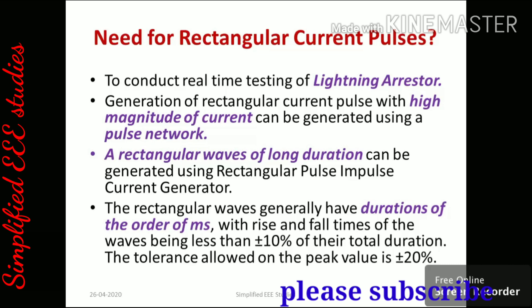It has more duration and a high peak value. The rectangular waves generally have durations in the order of milliseconds, with rise and fall times being less than plus or minus 10% of the total duration. The tolerance allowed on the peak value is approximately plus or minus 20%.